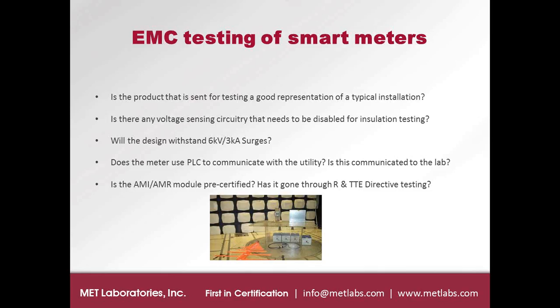Will the design withstand 6 kilovolts, 3 kiloamp surges? This is something that you need to cross-check in your design to see if it will meet the 6 kilovolt level. Are your MOVs or other arresters designed to meet the spec?